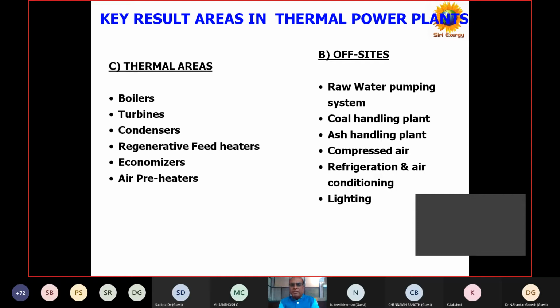So refrigeration and air conditioning is a huge requirement. Some of the plants may have almost more than 1,200 TR, that is tons of refrigeration load, because we have so many cooling needs, we have control rooms. Then also ESP, there is a control room, then again nowadays so many VFDs, variable speed drives, operating. For that again we require air conditioning, and also maybe window ACs or split ACs for the service building. So that is another major load.